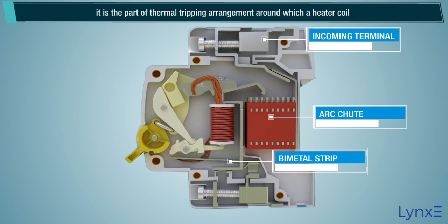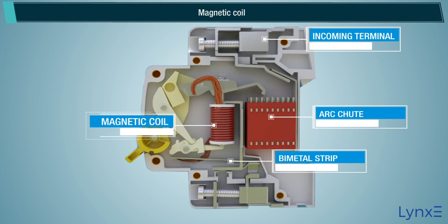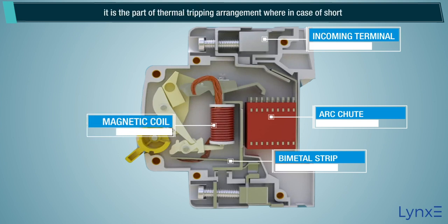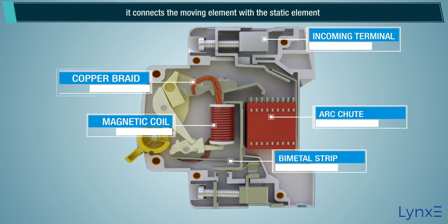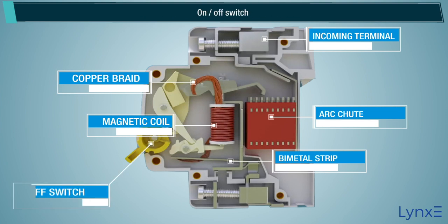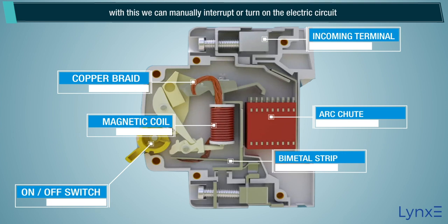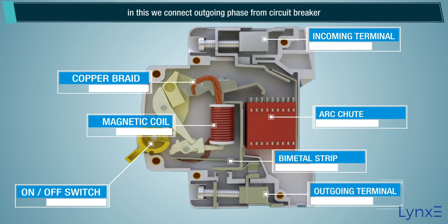Bimetal strip. It is the part of the thermal tripping arrangement around which a heater coil is wound to create heat depending on the flow of current. Magnetic coil. It is the part of the tripping arrangement where, in case of short circuit, a strong magnetic field is produced in the coils. Copper braid. It connects the moving element with the static element. On/off switch. With this we can manually interrupt or turn on the electric circuit. Outgoing terminal. In this we connect the outgoing phase from the circuit breaker.